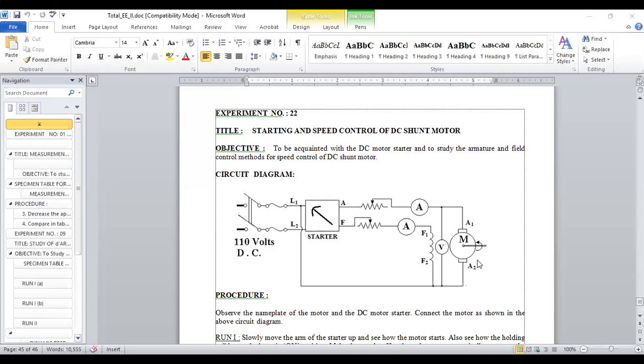Now, as I told you, to avoid the starting problem, we generally use a 4-point starter. Now, in the figure, you can see the 4 points. What are the 4 points? L1, L2, A, and F. So therefore, it is called the 4-point starter. It has 4 terminals, named L1, L2, A, and F. Now this L1 and L2 will be directly connected with the source, the voltage source, or the supply voltage. A will be connected with the armature, F will be connected with the field. So therefore the names are A and F.